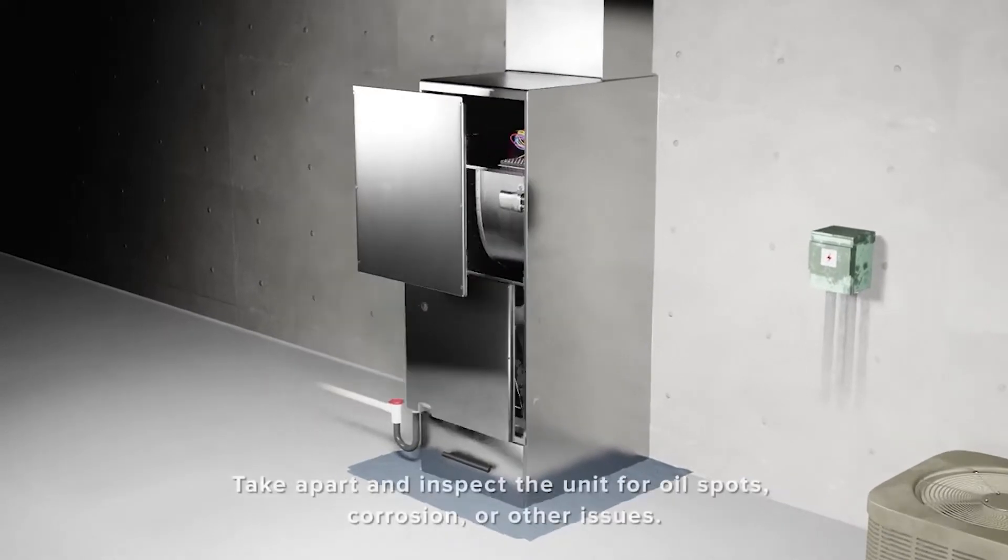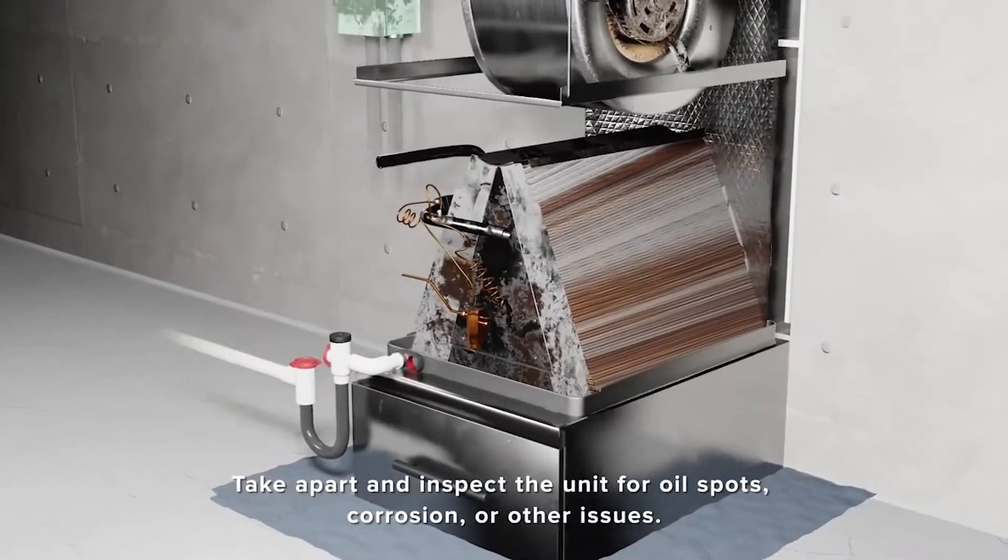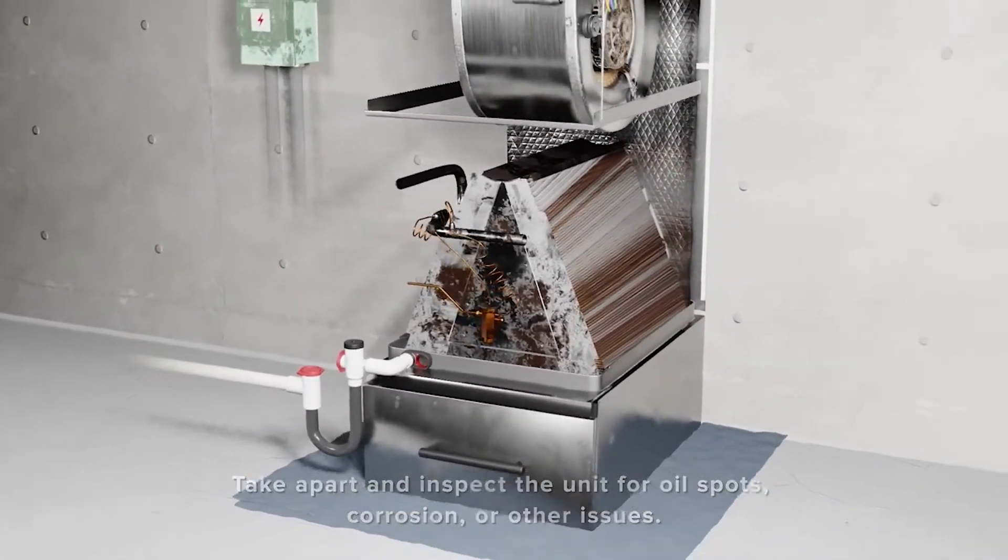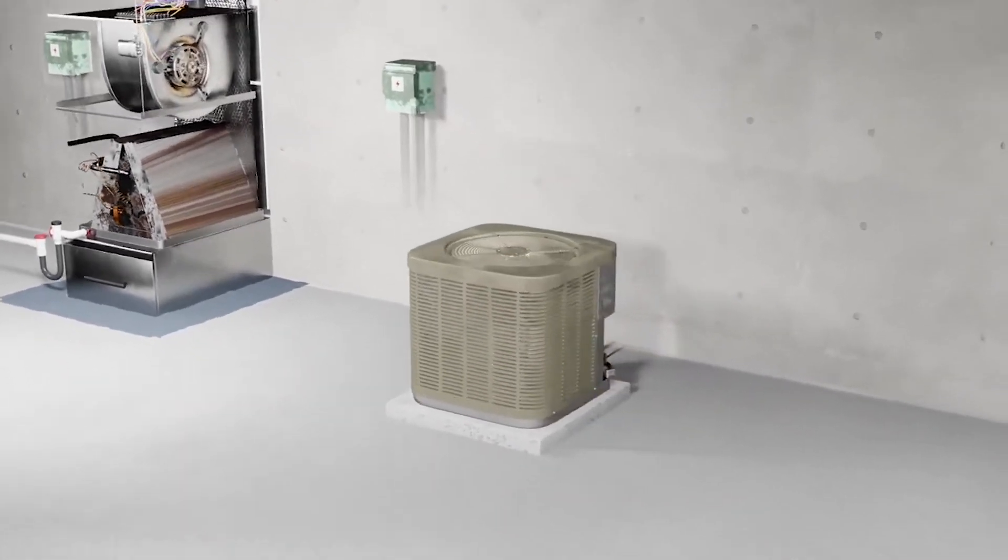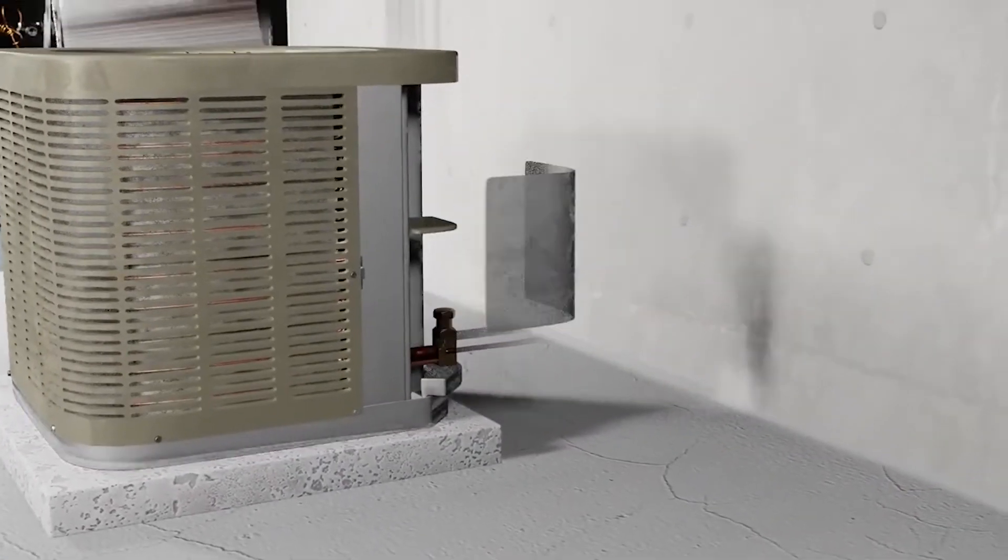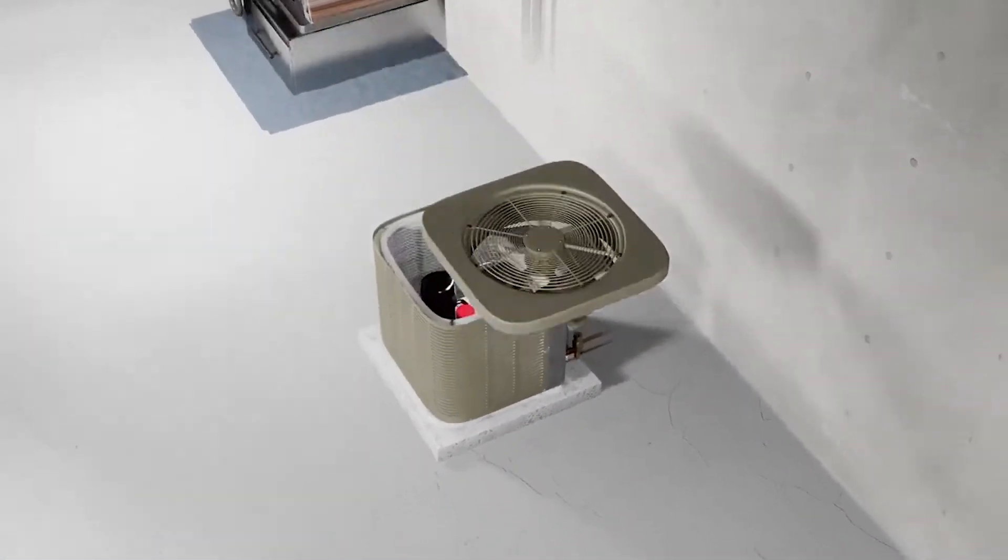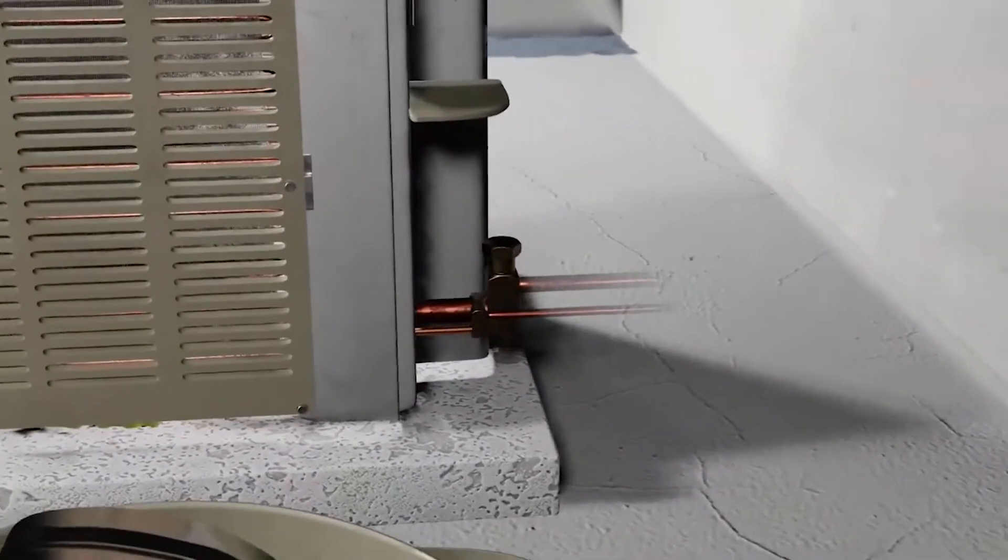Inspect the equipment and component cleanliness and condition. This includes the blower wheel, the evaporator coil, and the condenser coil. Pay attention to any signs of oil spotting, which may indicate refrigerant leak points.